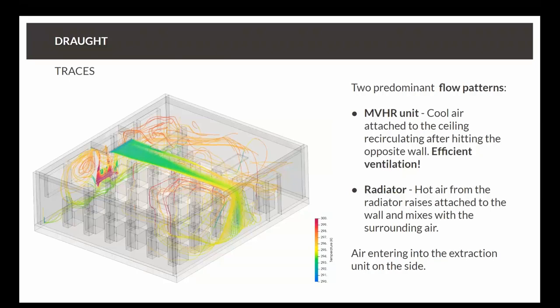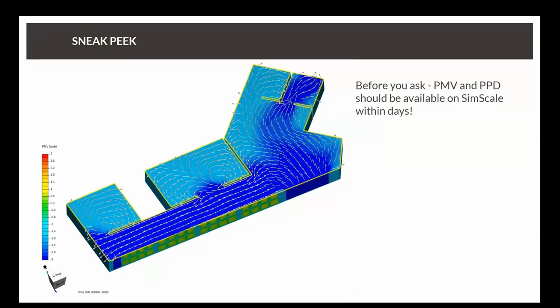Finally, some traces, as I showed in the post processor in the platform, where we can see these main flow patterns with the Coanda effect, with the flow going up from the radiator, hitting everything, the flow getting back to the unit. But you don't see any more draughts around the room. That's what we want to avoid. So, just to finish, and before everybody asks, we have some good news. We will be able to have PMV and PPD available in our platform within the next few days. So, that would be great to be able to see all these pictures that we have to take from an external post processor. That would be really useful for this kind of HVAC simulations.